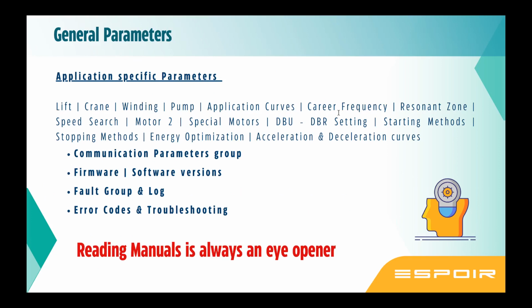There are special motors you need to tune. Then DBU DBR is recommended, but you need to set the parameters, set the limits. You have to enable it. By default, it is not enabled. You need to enable it.